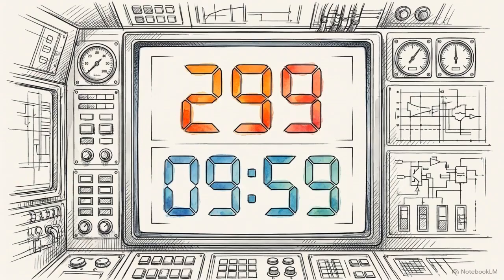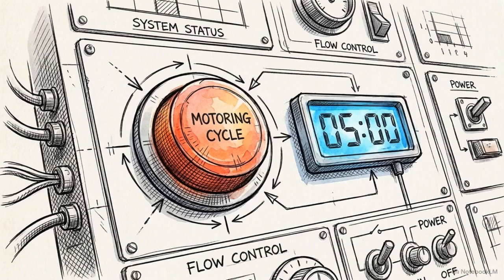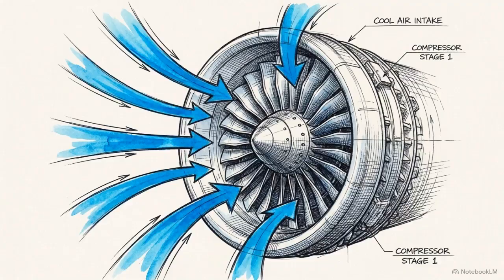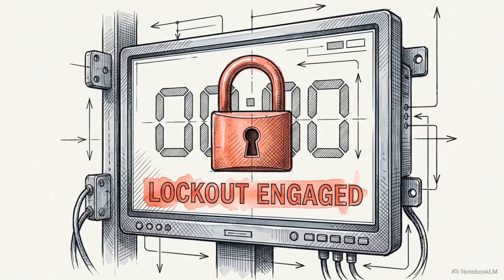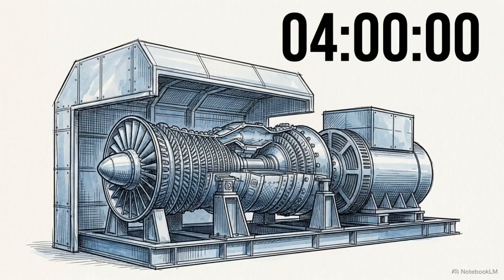When the coasting rotor drops to a low 300 RPM, the control system starts a 10-minute countdown clock. To restart safely, operators must initiate a 5-minute motoring cycle before the timer expires. This uses the starter to force cool air through the core, restabilizing the internal clearances. If that 10-minute window is missed, the system enforces a hard 4-hour lockout. This forces the unit to sit idle until the rotor and casing cool down and equalize naturally.